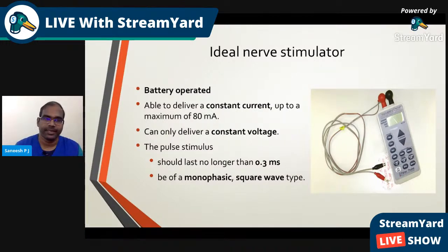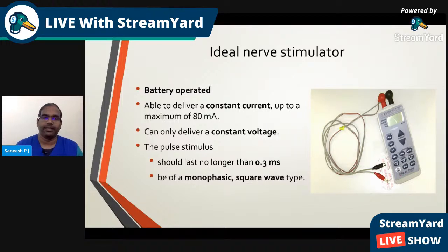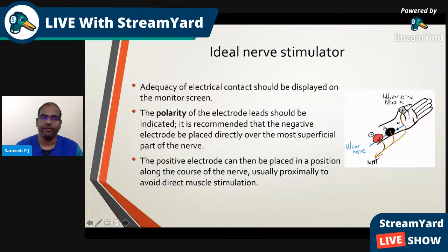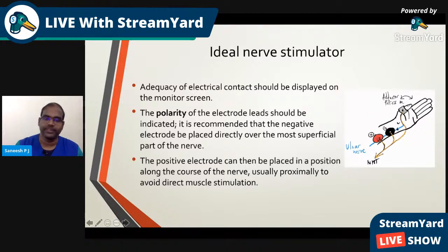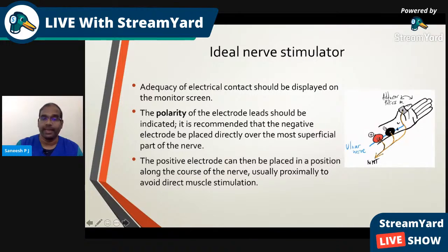The characteristics of an ideal nerve stimulator: it should be battery operated and deliver a constant current up to a maximum of 80 milliamperes. The pulse stimulus should last no longer than 0.3 milliseconds and be of a monophasic square wave type. The adequacy of electrical contacts should be displayed on the monitor screen and the polarity of electrode leads indicated. It is recommended that the negative electrode be placed directly over the most superficial part of the nerve, with the positive electrode placed proximal to avoid direct muscle stimulation.